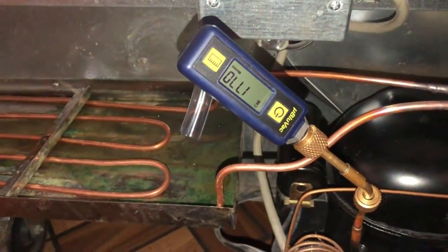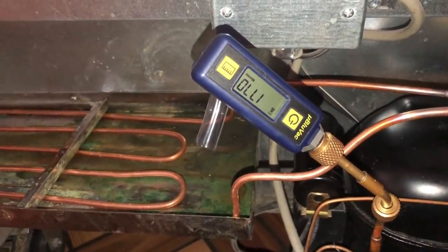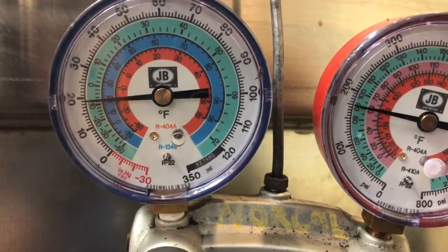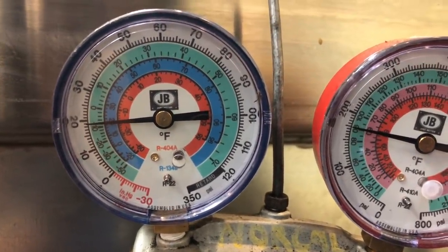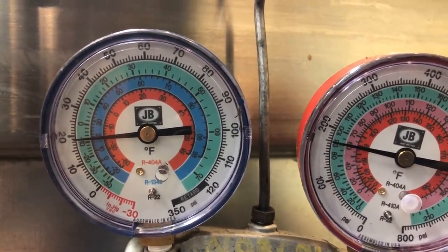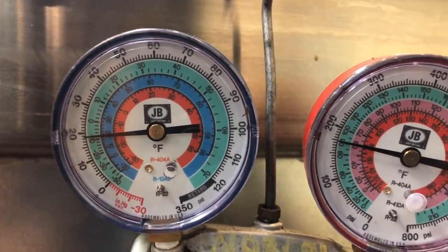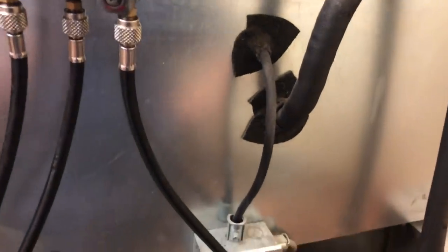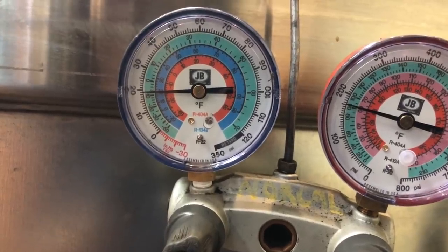I'm 13 minutes in and now I'm down to 1,770. Total time on the vacuum ended up being about 59 minutes total. I notice the head pressure on these little buggers usually runs a little high, but not too alarming. Not bad. You can send that to the bottles right now.